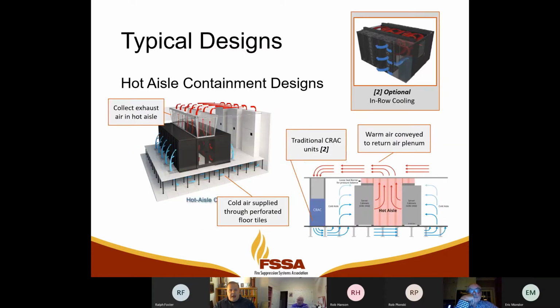What is more comfortable is this hot aisle containment, where you blow the cooling air into the room, which is more comfortable for people, and then it sucks through where the hot faces are facing each other, and then we actually duct it in some way. Like here, they're using clear plexiglass and some aluminum framing to duct the air up into a ceiling plenum, and then the separation is the ceiling really between the room and the ceiling plenum to get that air back into the CRAC units, which are then ducted up into the ceiling to get that to happen. You can kind of see that in section view over here.